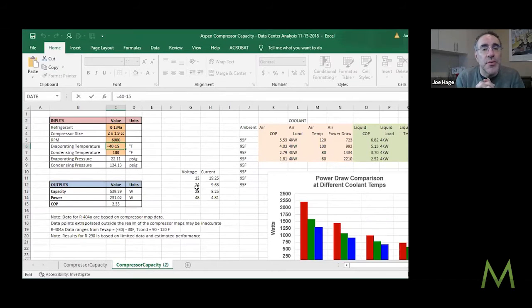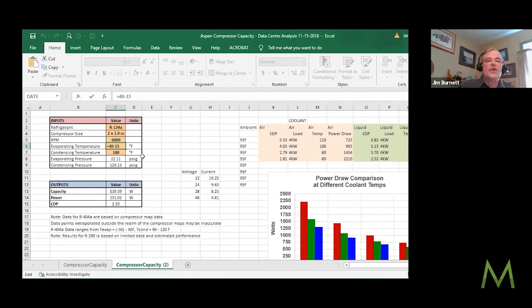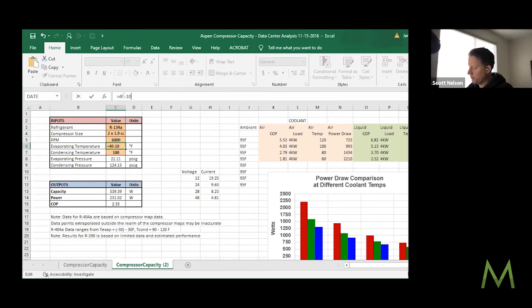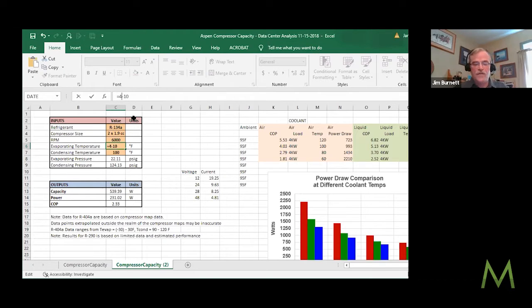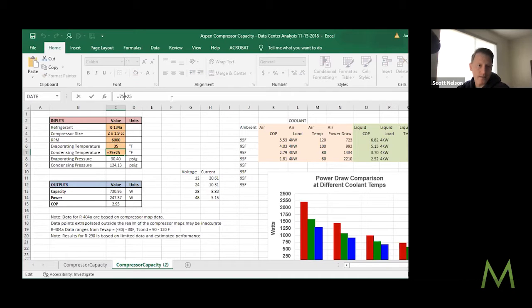You can see an Excel spreadsheet now. My inputs are here: refrigerant type, compressor size, which we'll play with, and evaporating temperature—this is the refrigerant temp. I'll use a 10 degree F delta T because I need to run my refrigerant colder than the liquid to get heat transfer. Delivered temperature was 45, so 45 minus 10. And what's your ambient air temperature? Let's go with 68.